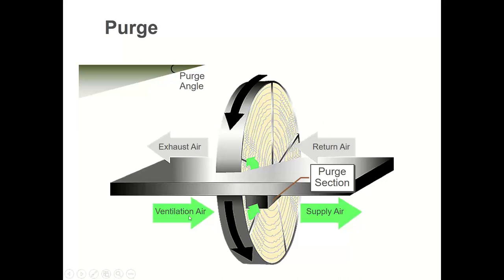Well, if I warm up the outside air coming in upstream of this wheel, and this wheel is a 70% effective wheel, that means 70% of the BTUs are going to go that way and leave the building, and only 30% go into the space. It thawed the wheel, sure, but only 30% of the BTUs went into my space. If I heat this return air, it'll also thaw the wheel, but 30% is going to leave and 70% is going to come back around. So don't ever put the heater on the ventilation inlet side, put the heater on the return air exiting side upstream of the wheel.